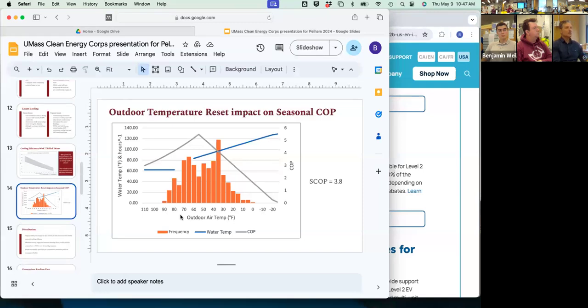But what that means is that we can probably do almost all the cooling with those ventilation units. They're doing all the dehumidification, which is most of it. And they're also providing some sensible cooling because they're delivering air at around 55 degrees. So the net result is the chiller part is like a little bonus, and it helps for the side of the building that maybe gets a lot of sun, or might have some sort of high sensible load. But especially during the school year, these are the temperatures before, and that's where humidity is much bigger part of it.